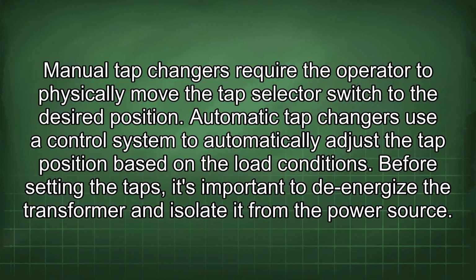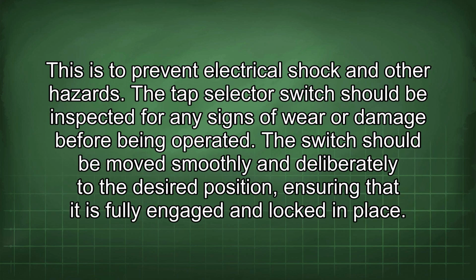Manual tap changers require the operator to physically move the tap selector switch to the desired position. Automatic tap changers use a control system to automatically adjust the tap position based on the load conditions. Before setting the taps, it's important to de-energize the transformer and isolate it from the power source. This is to prevent electrical shock and other hazards.